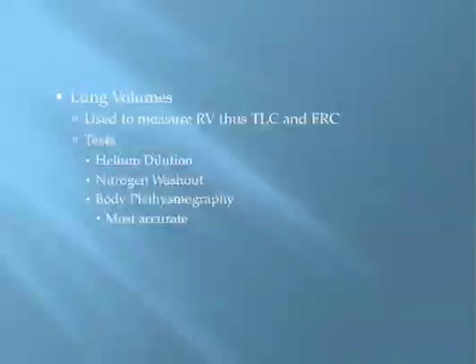The body box works on that very same principle. And because it's purely looking at what we call movement within the box and the barometric pressure and what happens with those pressures and volumes within the box as the patient's breathing in or out, it is able to determine true total lung capacity. It doesn't have to be in communication with airways that have air trapping. It can measure true total lung capacity.